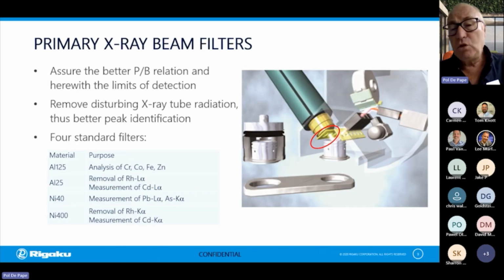So after the X-ray tube, the X-ray beam filters are placed. X-ray beam filters are used, first of all, to improve the peak to background ratios, to reduce the limits of detection, but also to remove disturbing X-ray tube radiation lines. So we are talking about a rhodium anode, and these rhodium lines can appear in spectra. If we want to analyze elements like rhodium, by means of filters, we can get those lines out of our spectrum.